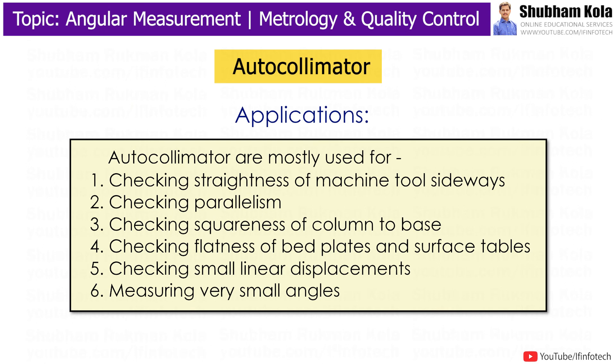Autocollimators are mostly used for checking the straightness of machine tool slideways, checking parallelism, checking squareness of column to base, checking flatness of bed plates and surface tables, checking small linear displacement, and measuring very small angles.